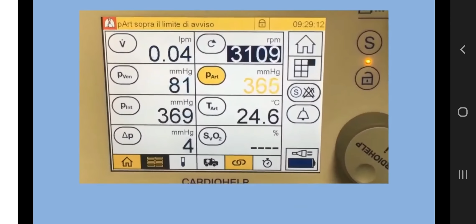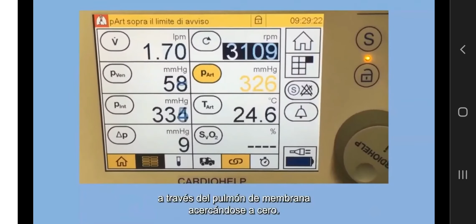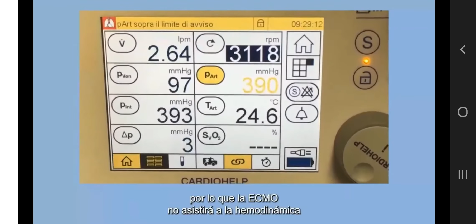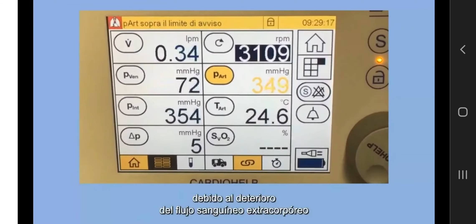With any obstruction occurring after the membrane lung, pre- and post-membrane lung pressures will severely increase, with the pressure drop across the membrane lung approaching zero. We have no flow, so ECMO will fail in supporting hemodynamics or gas exchange or both. Moreover, blood stagnation due to impaired extracorporeal blood flow may lead to intra-circuit thrombosis.